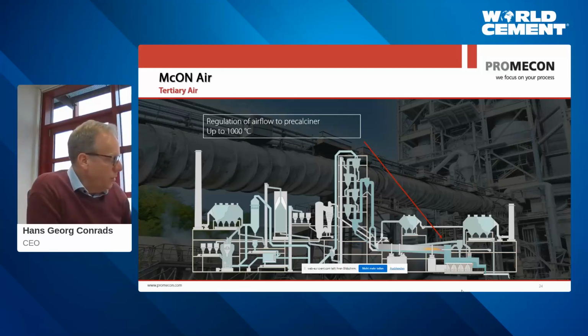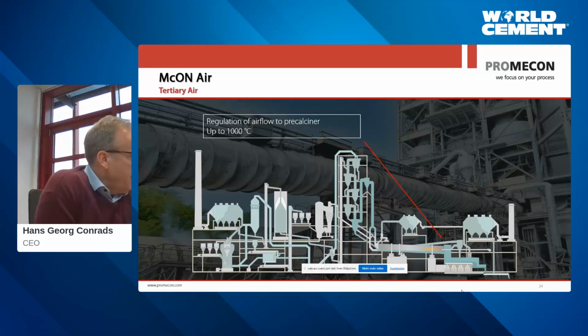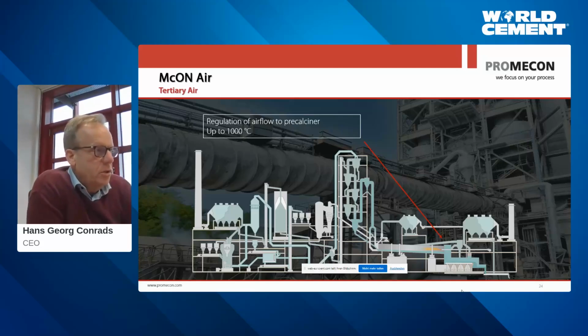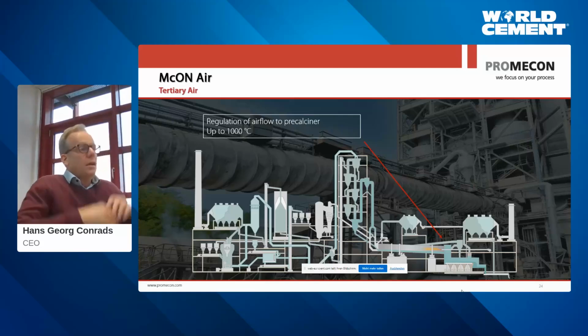I need to say something to you that I have not mentioned yet, which is new. Besides the antenna measurement that I have talked about, PROMECON also has an infrared measurement that we are offering, especially for tertiary air ducts that have a very high dust level contact, because it can be very abrasive, can be very hard to measure. And we found that the infrared measurement is a perfect measurement for this application. On top of that, you can get additional benefits such as temperature. And we are also looking into more elements that you might be able to measure at that location in the future. So tertiary air measurement is a very hot candidate for more applications in the future than just flow. But for now, what we are giving you is flow into the precalciner.